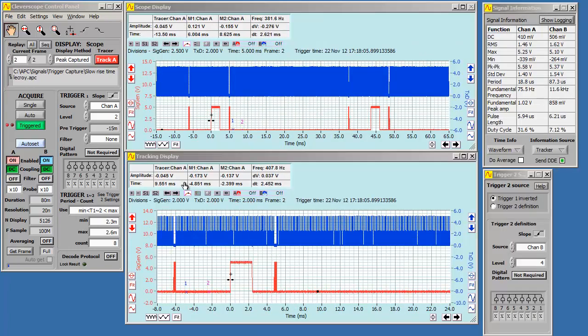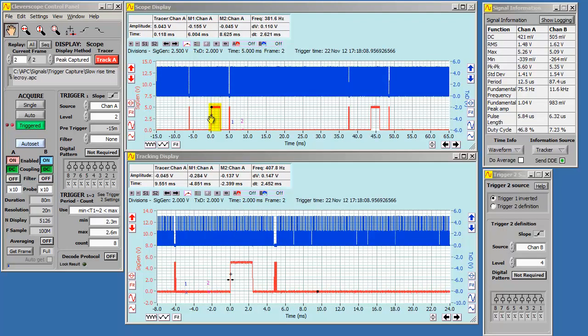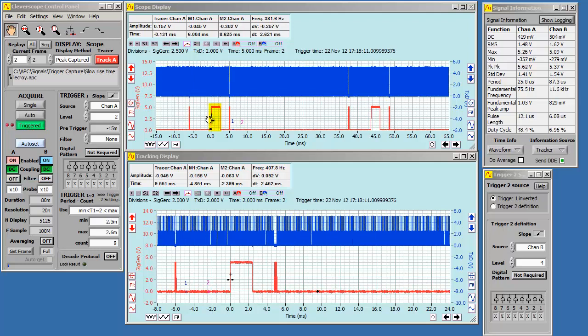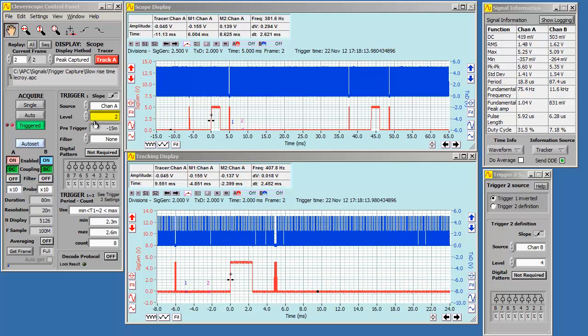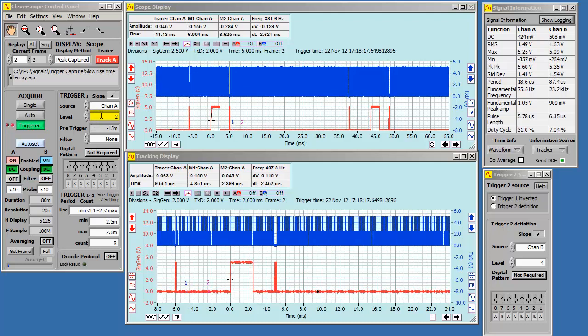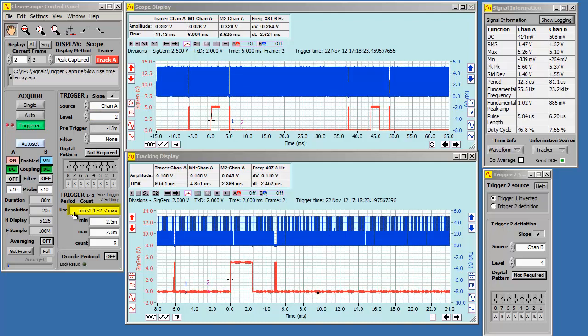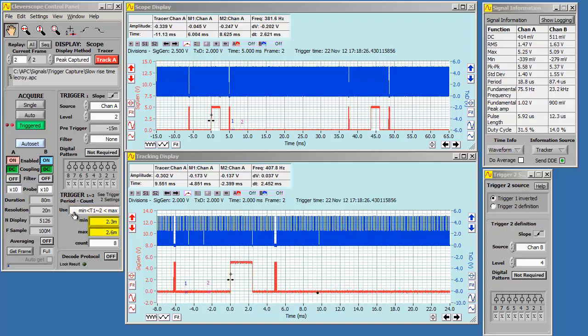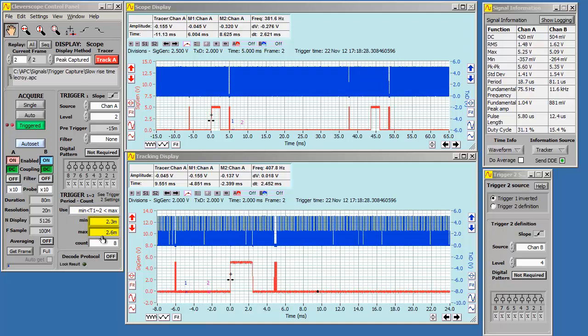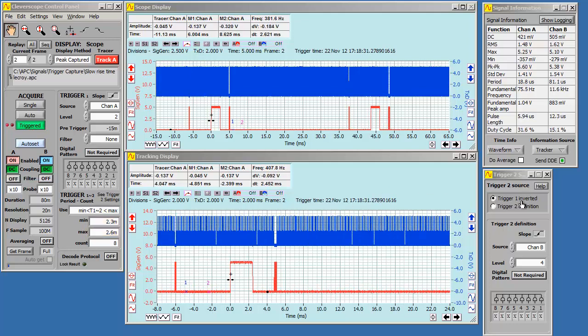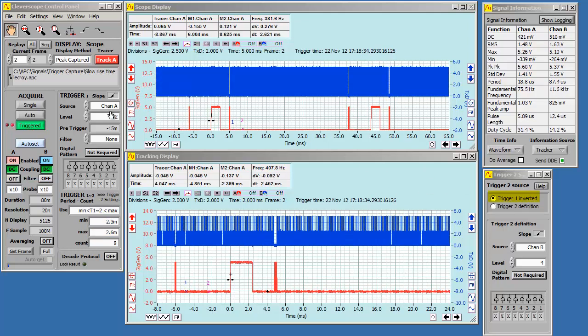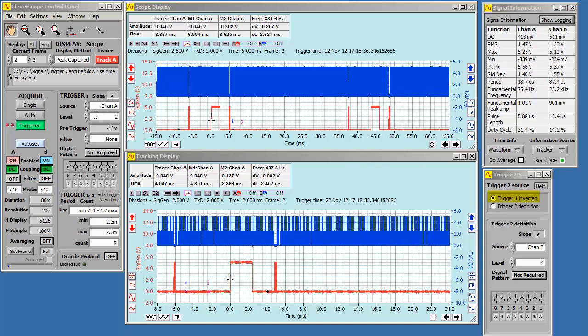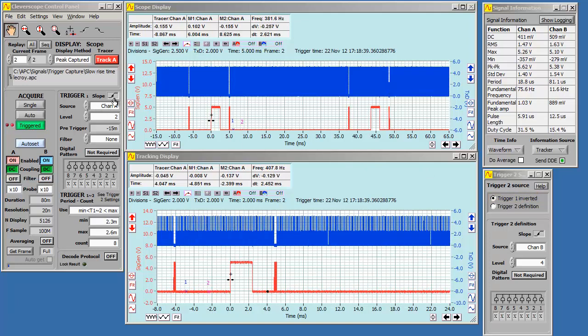One final look. In this example, we are triggering on a 2.5 ms wide pulse on channel A. We are using both triggers again, with channel A triggering rising through 2 volts. We are using the range of times between 2.3 and 2.6 ms. Trigger 2 is set up to be trigger 1 inverted. In other words, through channel A, 2 volts, but with a falling edge instead.